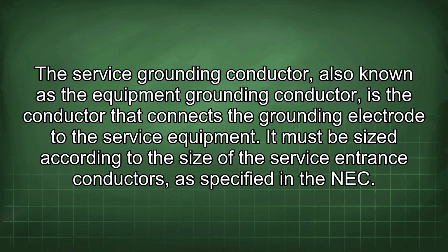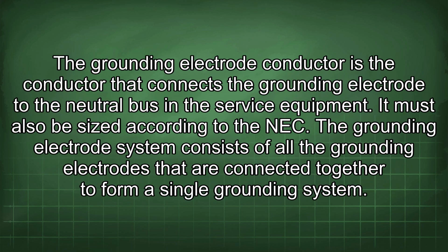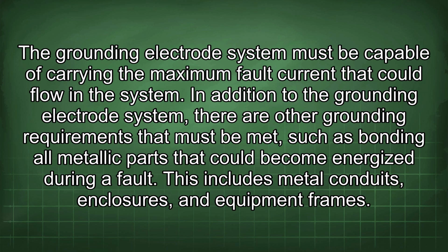The service grounding conductor, also known as the equipment grounding conductor, is the conductor that connects the grounding electrode to the service equipment. It must be sized according to the size of the service entrance conductors, as specified in the NEC. The grounding electrode conductor is the conductor that connects the grounding electrode to the neutral bus in the service equipment. It must also be sized according to the NEC. The grounding electrode system consists of all the grounding electrodes that are connected together to form a single grounding system. The grounding electrode system must be capable of carrying the maximum fault current that could flow in the system.